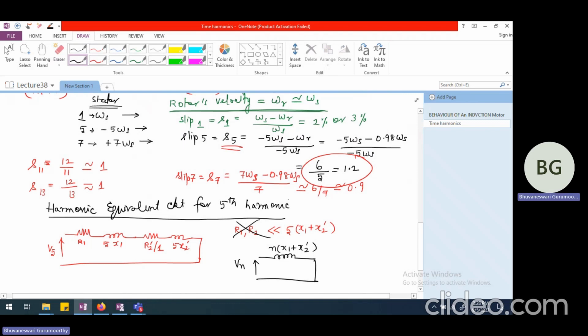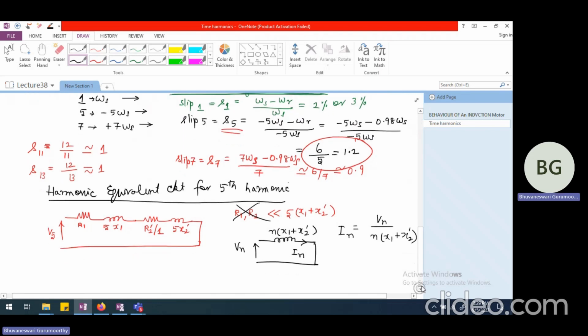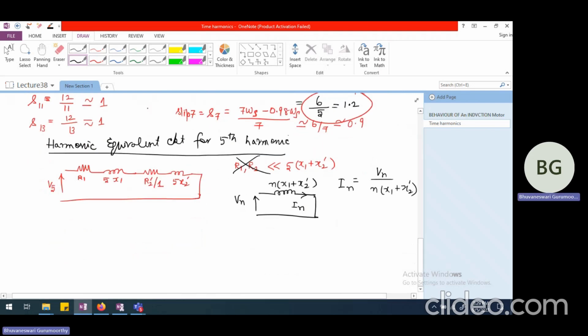This is the overall equivalent circuit, and the current circulating here is In. So the nth harmonic current In equals Vn divided by n times X1 plus X2 dash. For a square wave inverter voltage, harmonic analysis shows that if V1 is 100%, then V5 is 1/5 of V1.